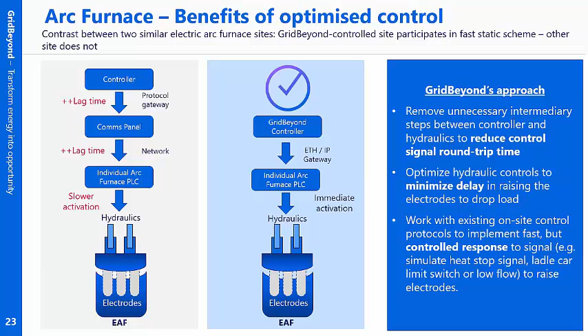We have looked at other options, like transformer tapping. We found them not to be fast enough. Not many sites out there have thyristor controlled transformers controlling their arc furnaces, but that would certainly deliver it. But again, it's going to site, seeing what control solution is there, and trying to use that to deliver the arc furnace into grid schemes. Wayne, I think that's it on that one, if you want to move on.